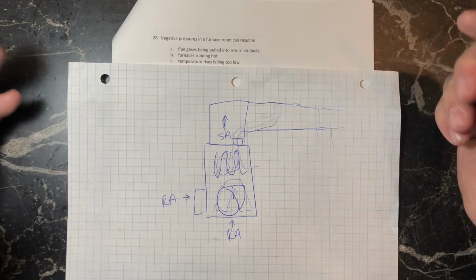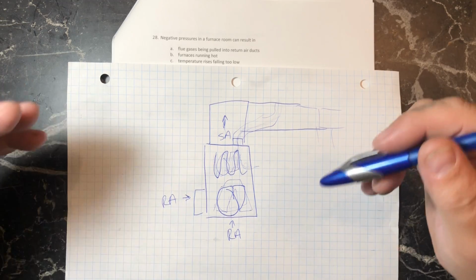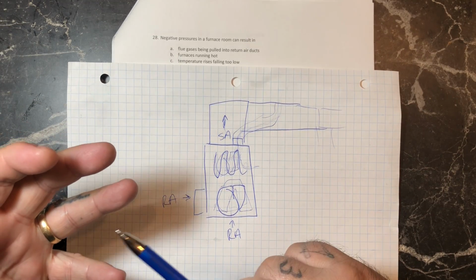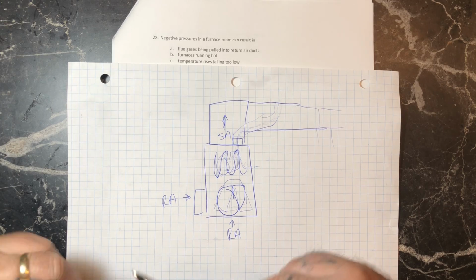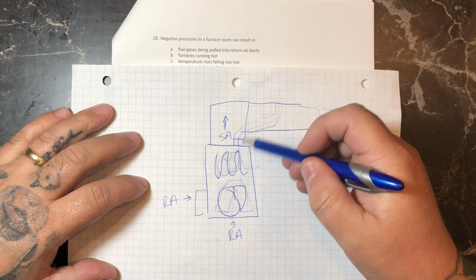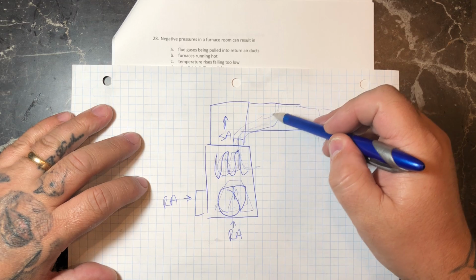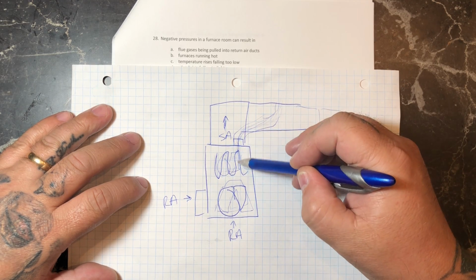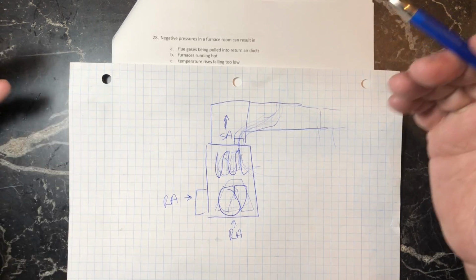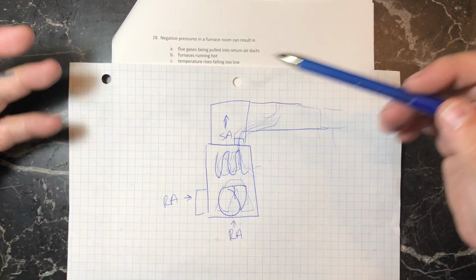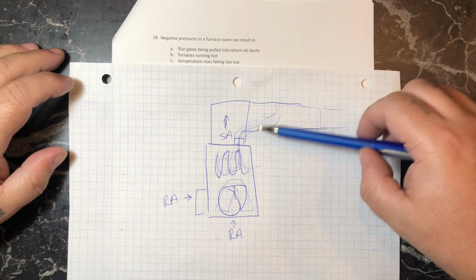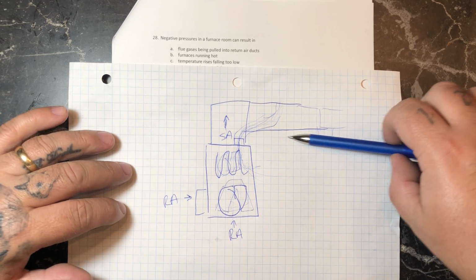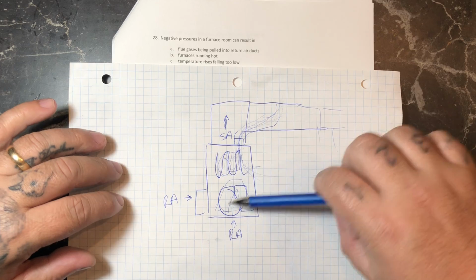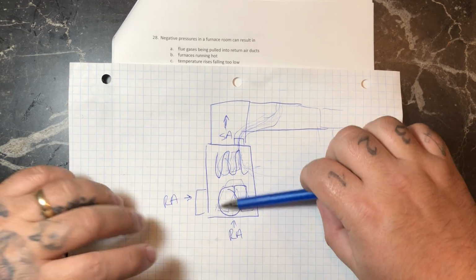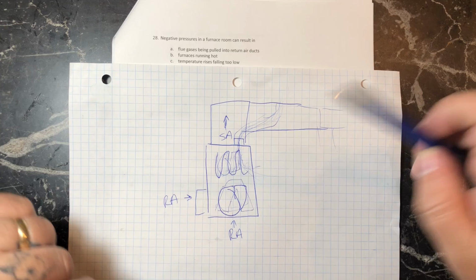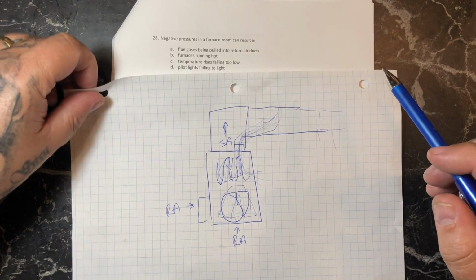If you had a negative pressure in your building, so in a house, if you had your dryer running and your bathroom fans running and the range hood running, you can cause a negative pressure in your house. That negative pressure can be enough that it would actually draw that poisonous gas back down into your house and potentially kill people. So that's called backdrafting. Higher efficiency furnaces now have a completely sealed unit, so they bring in their own fresh combustion air from outside and exhaust directly to outside, so there's no concern for negative pressure.